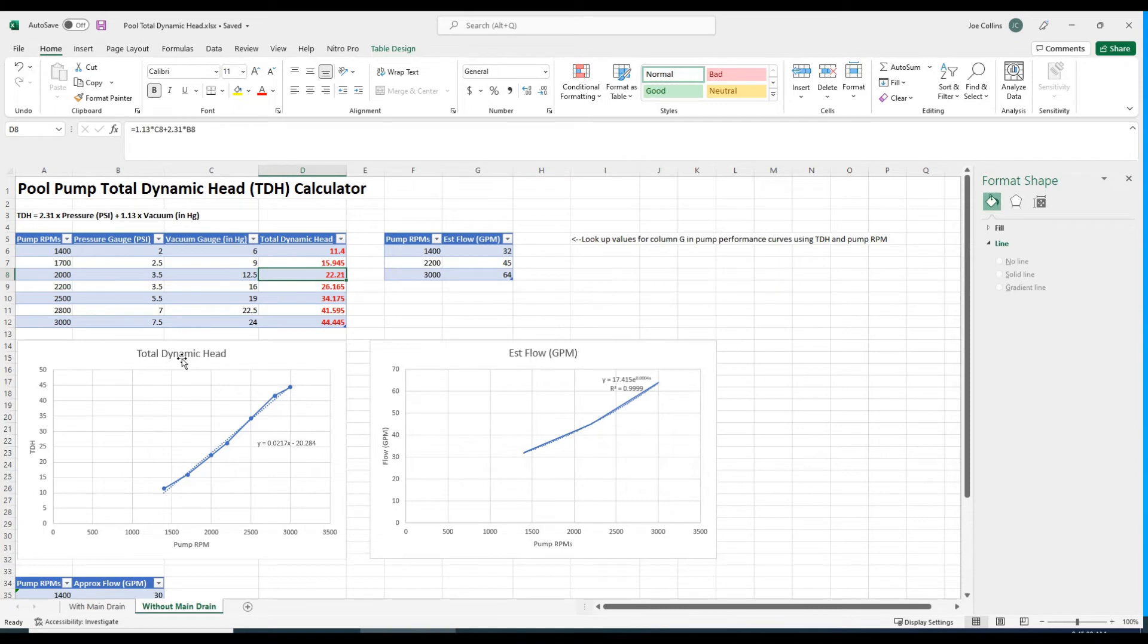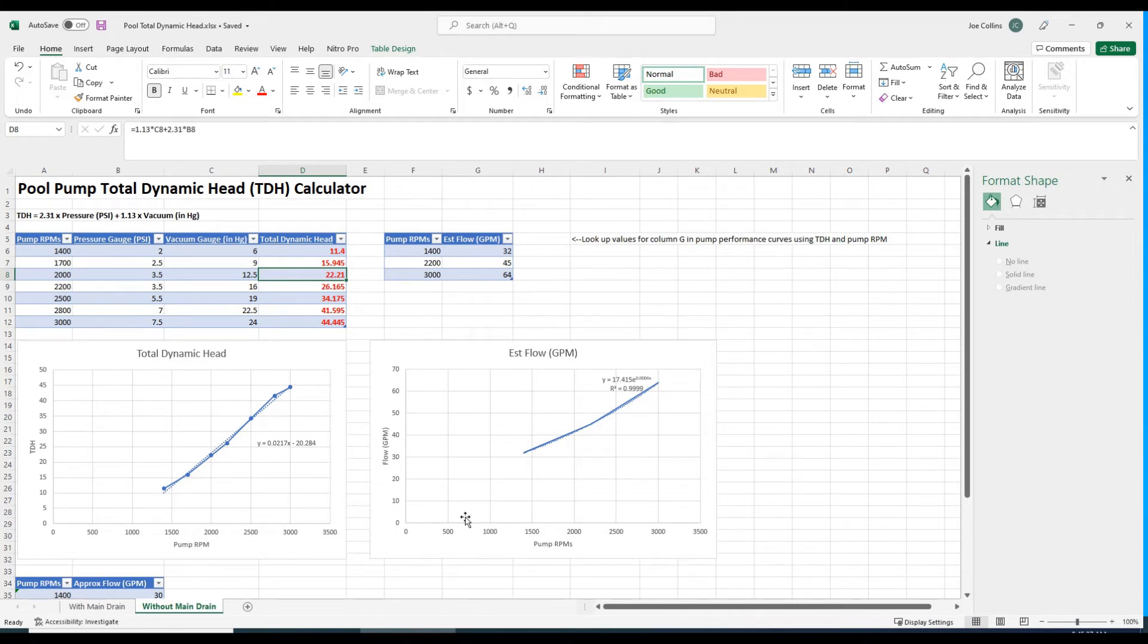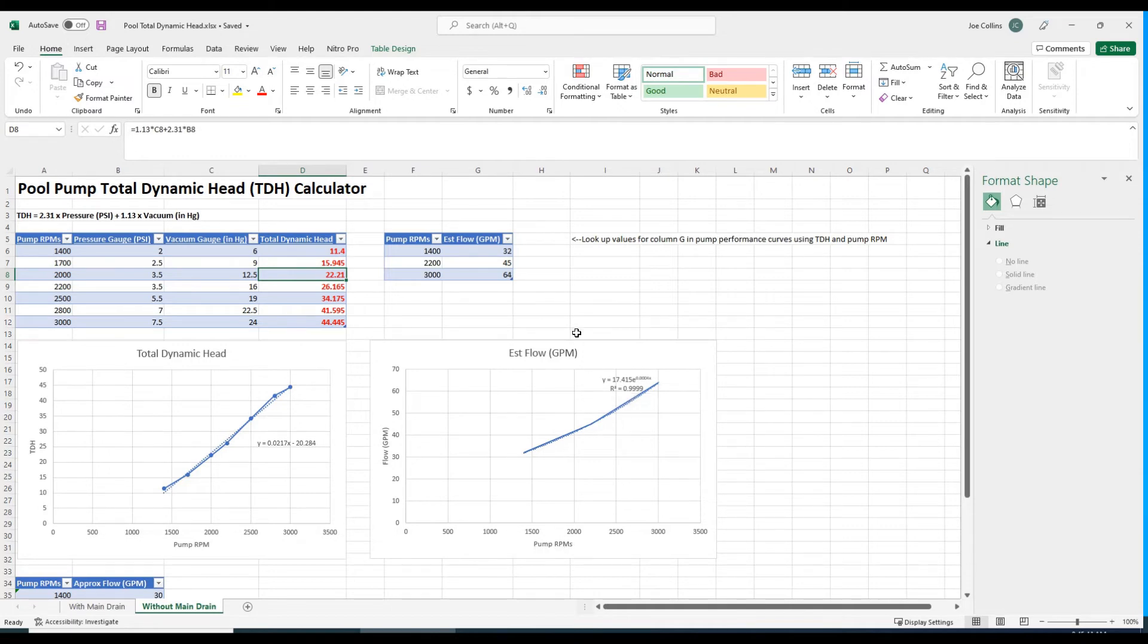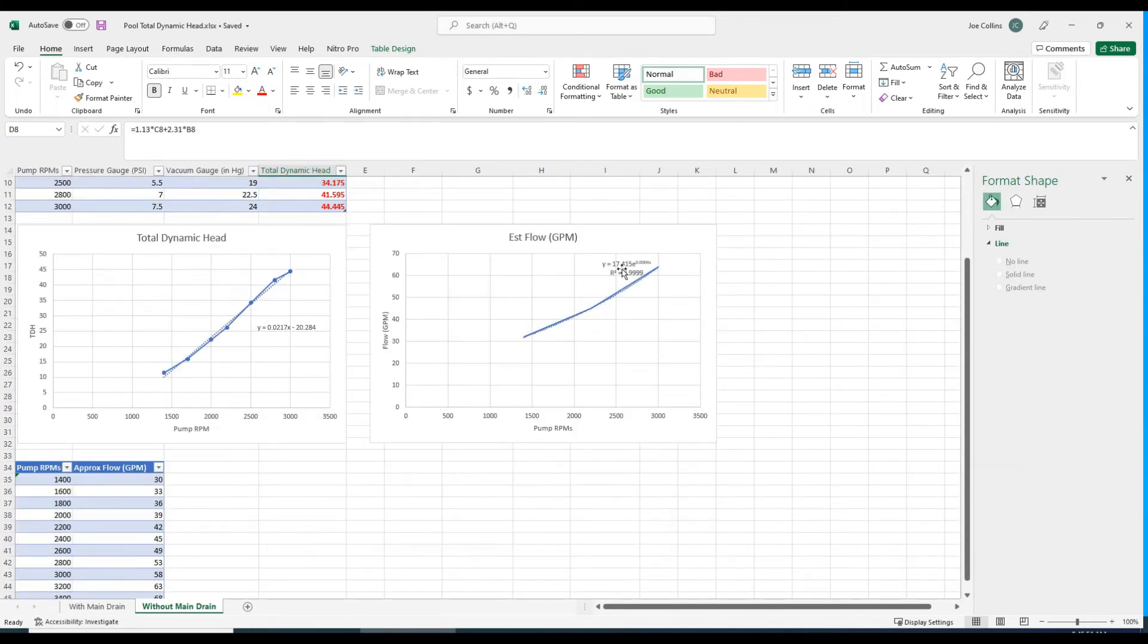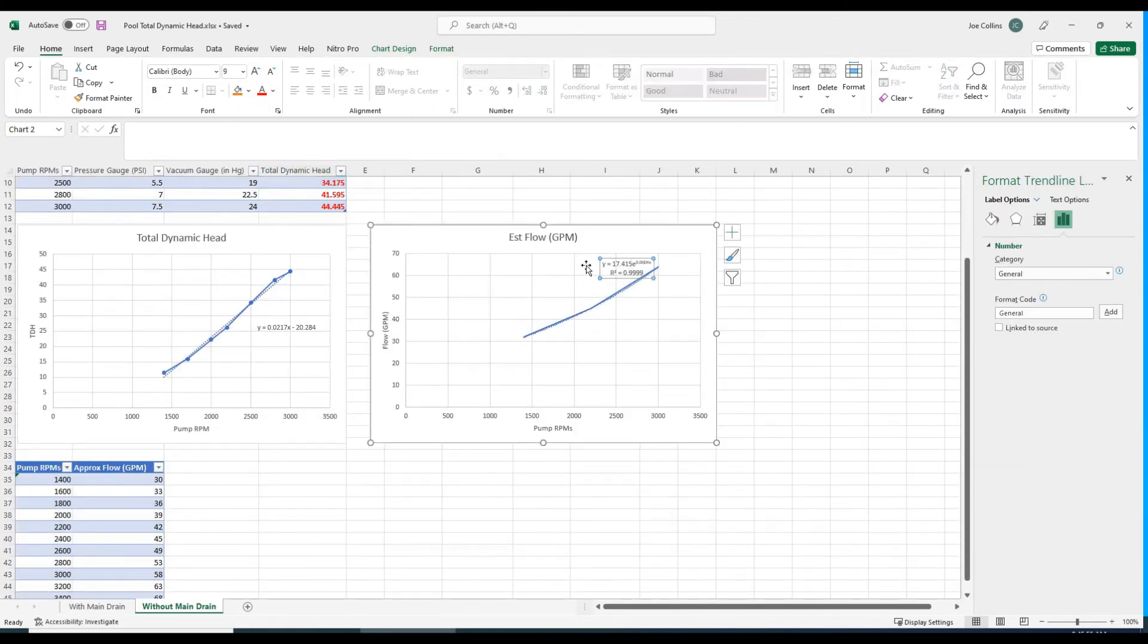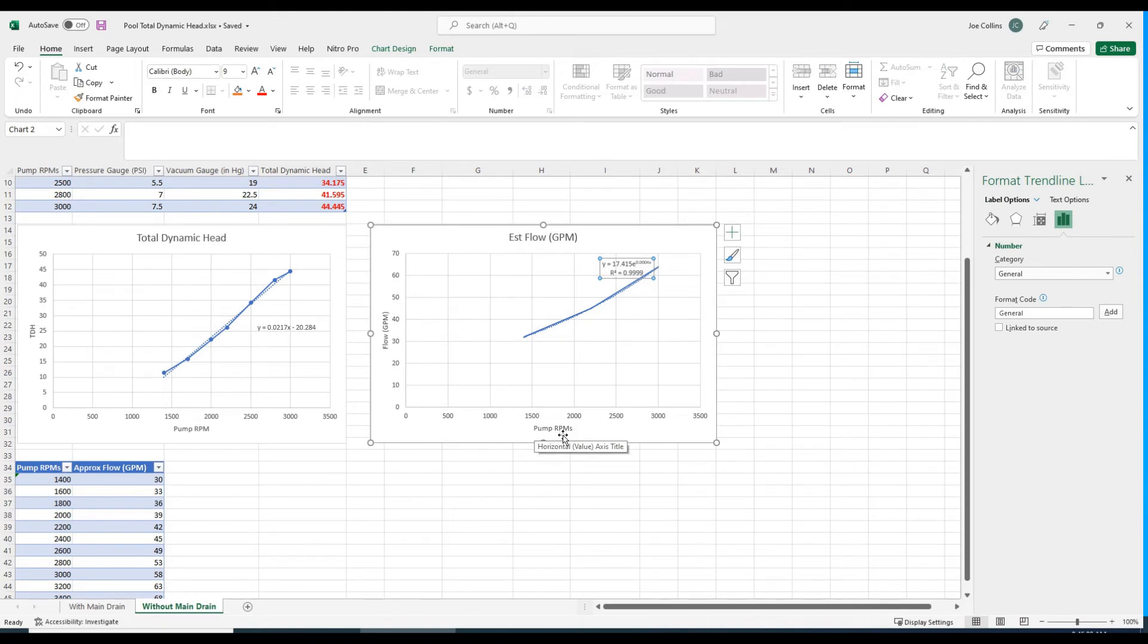I put in these graphs that chart the total dynamic head with pump RPM and also the estimated flow as read from that chart with pump RPMs. You may want to calculate the flow at some arbitrary RPM because they only give you three curves. For that, I set up a very simple regression model in Excel that charts using exponential regression analysis the pump RPMs with flow.